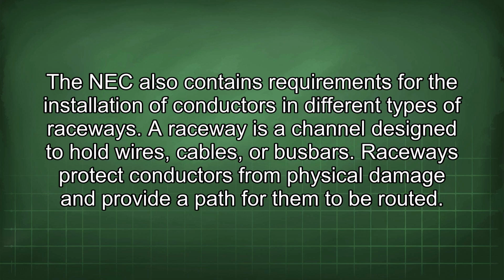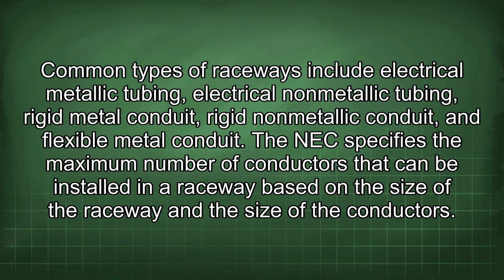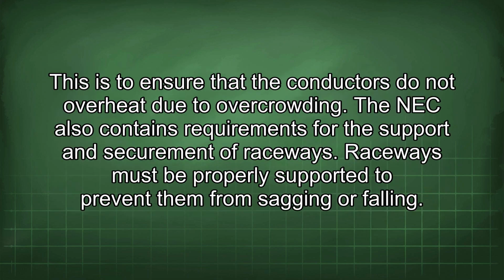The NEC also contains requirements for the installation of conductors in different types of raceways. A raceway is a channel designed to hold wires, cables, or busbars. Raceways protect conductors from physical damage and provide a path for them to be routed. Common types of raceways include electrical metallic tubing, electrical non-metallic tubing, rigid metal conduit, rigid non-metallic conduit, and flexible metal conduit. The NEC specifies the maximum number of conductors that can be installed in a raceway based on the size of the raceway and the size of the conductors. This is to ensure that the conductors do not overheat due to overcrowding.